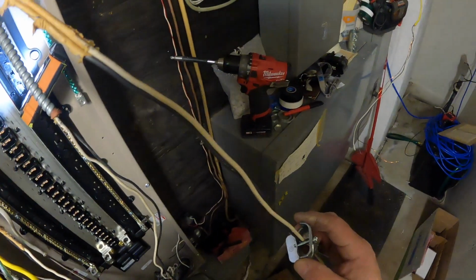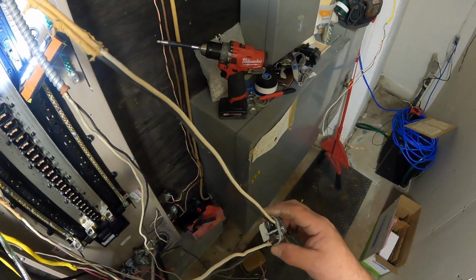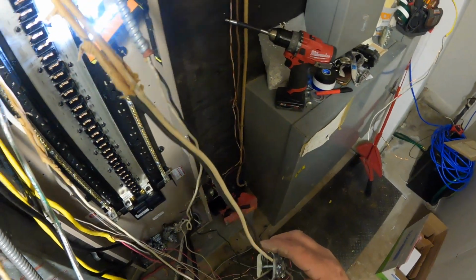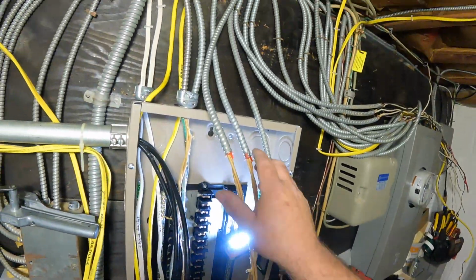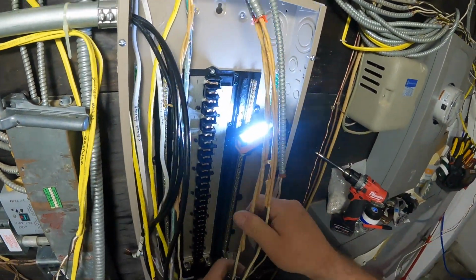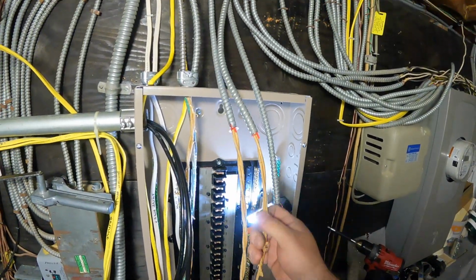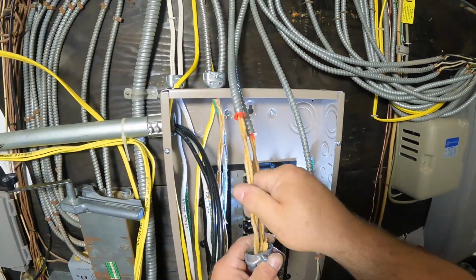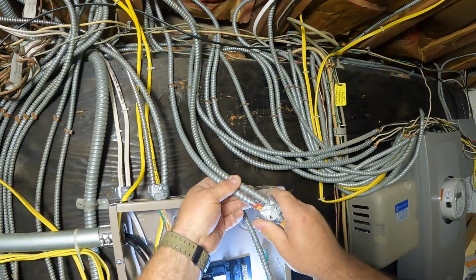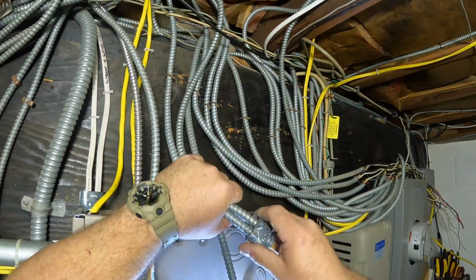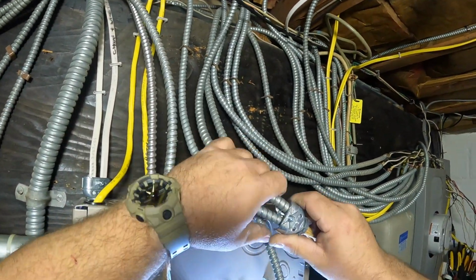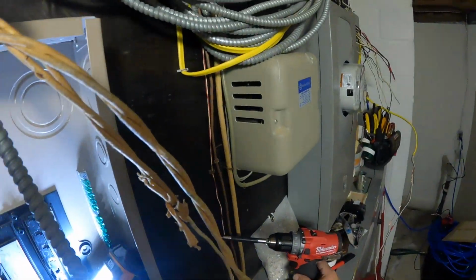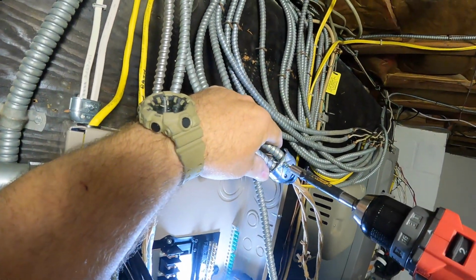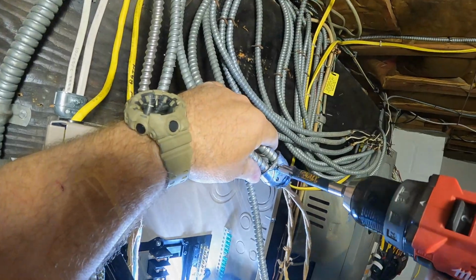Next step is to put both of these cables into the connector and slide the connector up into position and tighten it down. Now it's important that you tighten it down pretty hard around this BX cable, because that actually completes the equipment grounding path once you attach it with the lock nut to the enclosure. So make sure you get a nice tight fit here. You don't want to break the cable, but you want to make sure it's nice and tight because it serves a purpose.